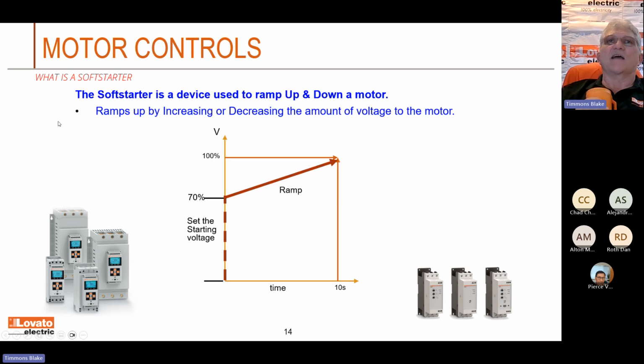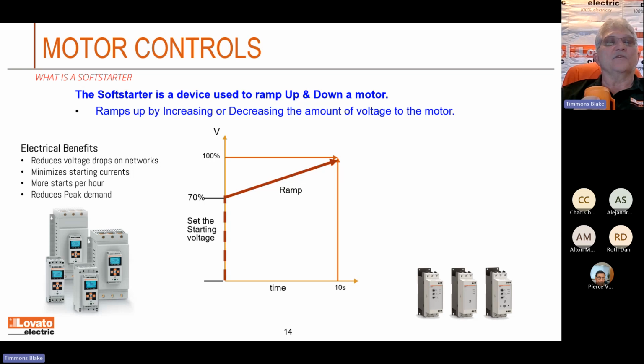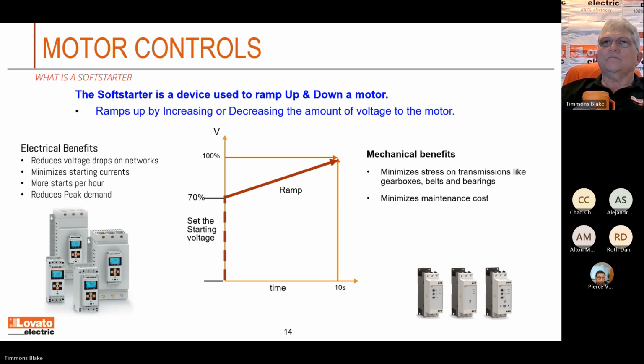Okay. Here's a diagram of how that works. So you have a starting voltage on a soft starter, and then you're going to ramp. And you can determine where that starting voltage is typically and how long the ramp is. See if I got an animation on that. It reduces voltage drops in the networks, minimizes starting current, allows more starts per hour doing that. It reduces the peak demand. Minimizes the maintenance.